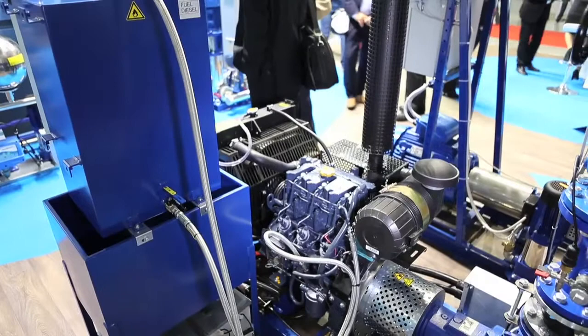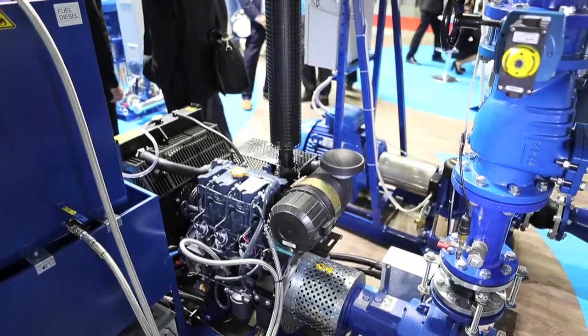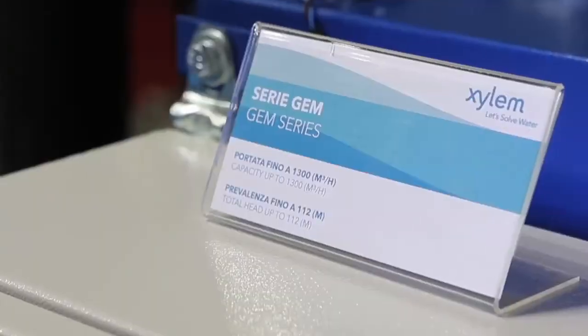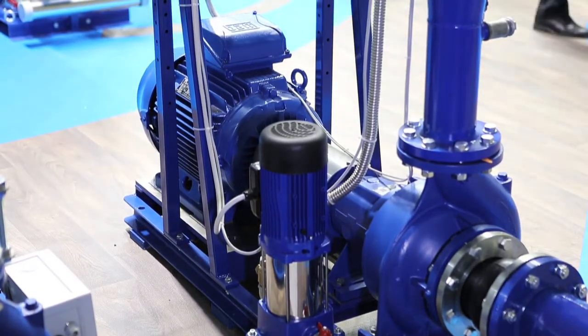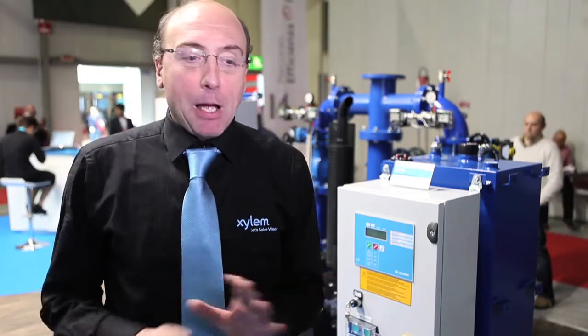The range of the Fire Set is arranged where we have electric pumps and diesel engine pump combined together. The duty point is about 1,300 cubic meter per hour and the head is about 10 to 11 bar. With these duty points we can cover all the inquiries of 80% of the fire system. According to this duty point we can choose the right pump with the power size of the pump.